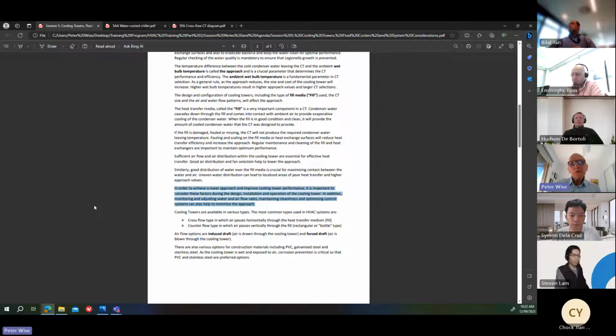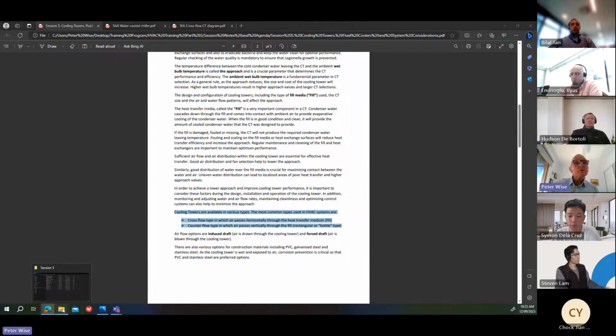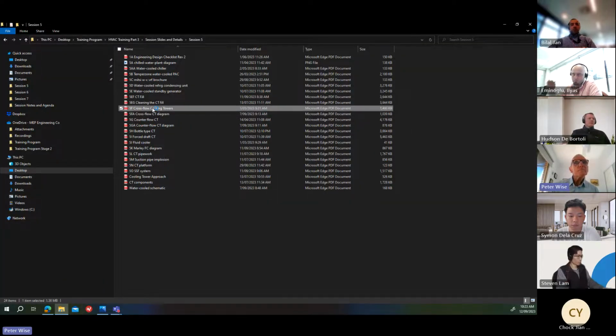In order to achieve a lower approach and improve cooling tower performance, it's important to consider these factors during design, installation, and operation. In addition, monitoring, adjusting water and airflow rates, maintaining cleanliness and optimising control systems can also help to minimise the approach. Cooling towers are available in various types. The most common types we use in HVAC systems are cross-flow. So I'll show you a picture of a cross-flow cooling tower.